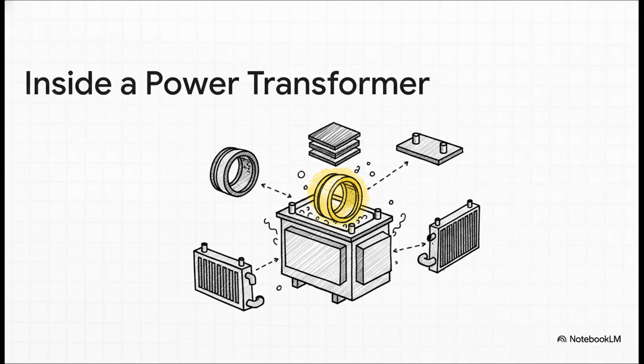During a fault, the system can get seriously unbalanced, creating these rogue currents called zero-sequence currents. Think of them as this chaotic electrical energy with nowhere to go. The tertiary winding provides a safe, closed loop for these currents to flow into, basically trapping and neutralizing them before they can cause a cascade of problems across the system.